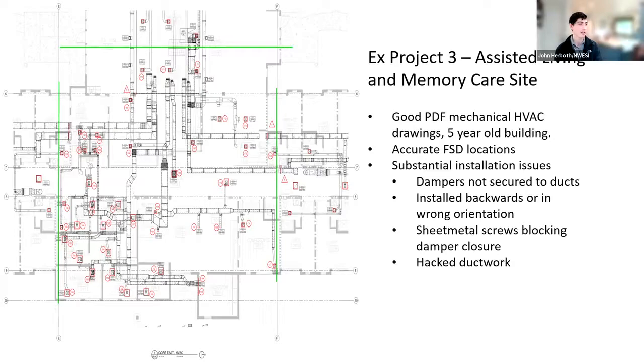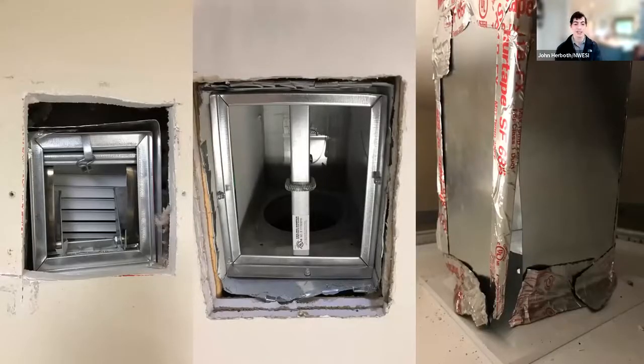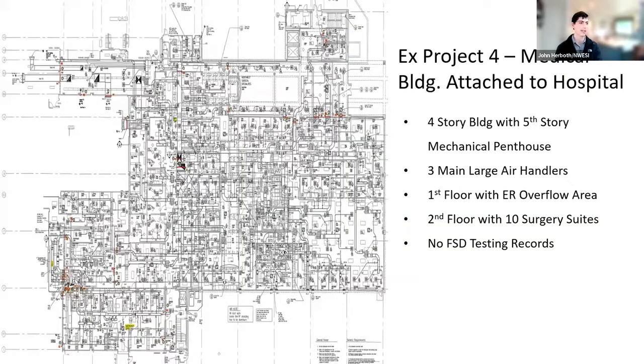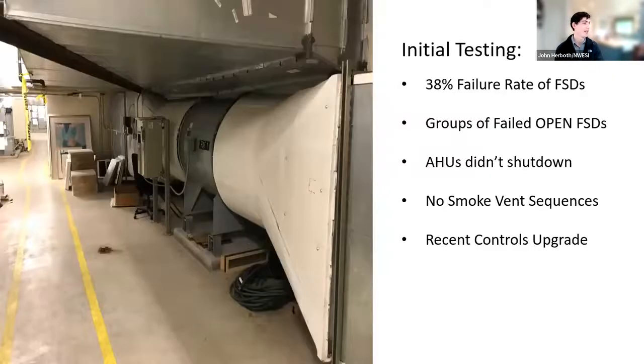You can have great documentation, great stuff for a fixed project, and then you come into installation that is just terrible and just almost negligent. I would say negligent on this one. And you have to have that conversation with the maintenance team as well as the owner, and then you have to go into potential litigation mode where you tell your team to be quiet in the field. You don't want to talk about it out loud. Just do your work and keep it professional as possible. And you can get medical buildings attached to hospitals where there's a question mark on you have an inherent fire alarm system taking control of everything and no records whatsoever, but you have ORs and stuff that should have smoke control systems, and it doesn't have any smoke control sequences. So it's fun. And then you can have those huge air handlers where you should never trust the safety devices on them. This was another high failure rate project. Air handlers didn't shut down, no smoke vent sequences.